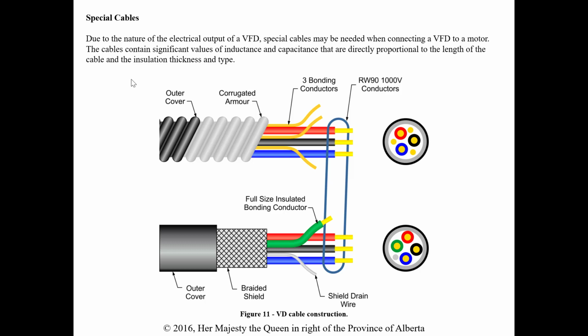Again, the cables contain significant values of inductance and capacitance that are directly proportional to the length. The cable run between the motor and the drive is seen as an impedance to the VFD. Whenever cable surge impedance does not match the surge impedance of the motor, a reflected wave occurs. Again, load reactors can be used between the drive and the motor to help reduce this problem. If we don't reduce it, those reflected waves can actually cause high spikes at the motor terminals, which can produce destructive conditions for the insulation. And then we get pitting, and that again is at the expense of the motor.